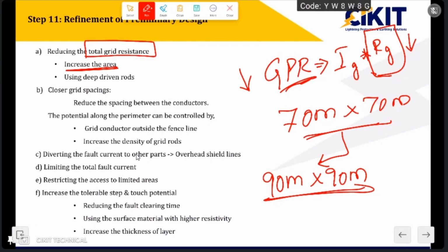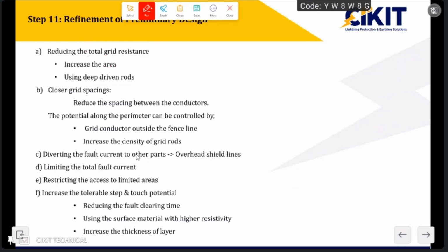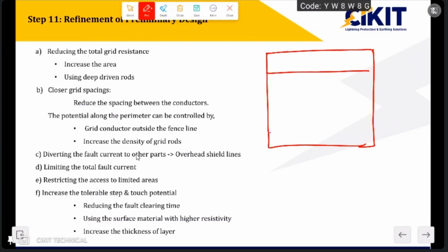So in areas where we don't have sufficient space, the alternate method provided by the standard is by using deep driven earth rods. We can provide earth rods at different places, like initially, if there is no earth rod in the design. I have mentioned in the previous slide, it is not mandatory to have these earth electrodes. So if I am performing this calculation and found that the values are higher, then what can I do? I can go for these earth electrodes.